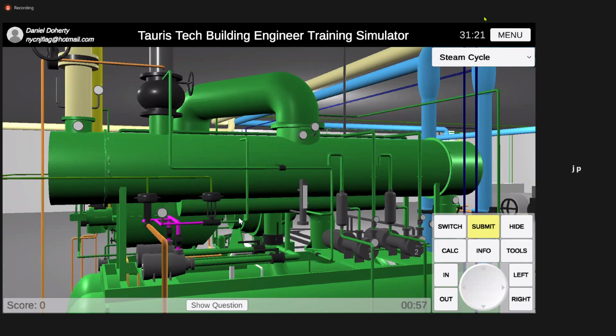If it gets too low, then the hot well's not filled anymore, so it's got to bypass the water. Correct. Yes, that's exactly it. That's it. So those two valves work opposite. When one's opening, the other one's closed. Correct. And vice versa. Yeah. They both can't be open at the same time. Either one's open and one's closed, or one's open and one's closed. You know what I'm saying? They're never going to be closed together. They're never going to be open together. You're either recirculating or you're dumping. Mm-hmm.